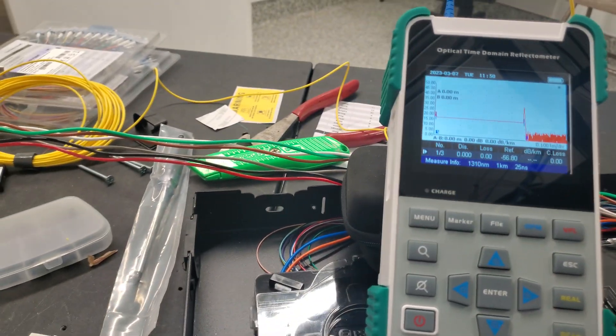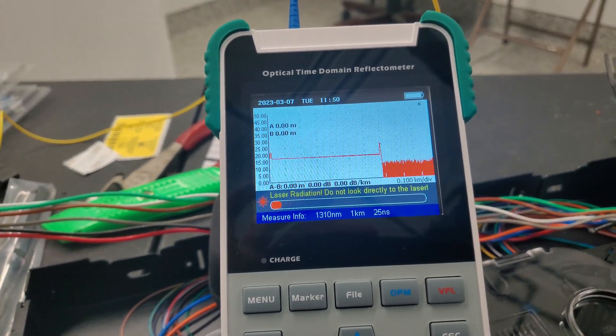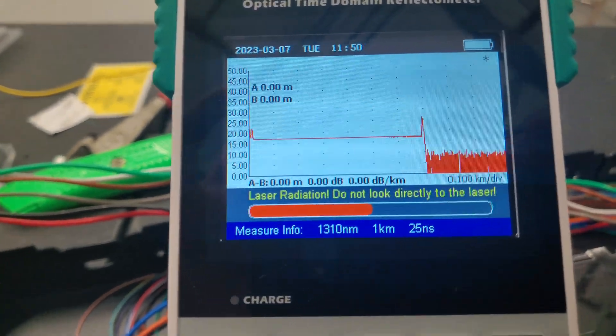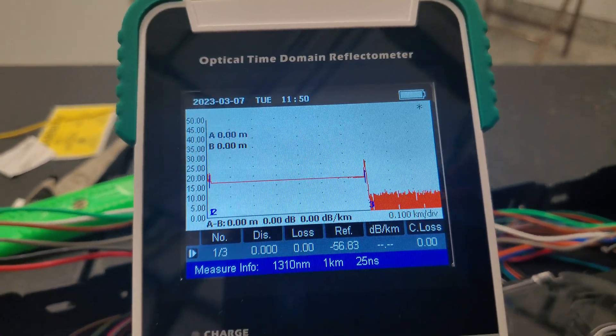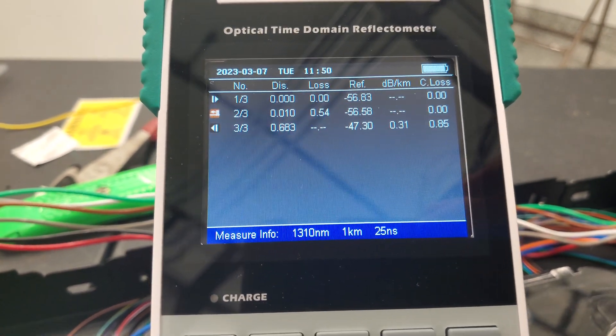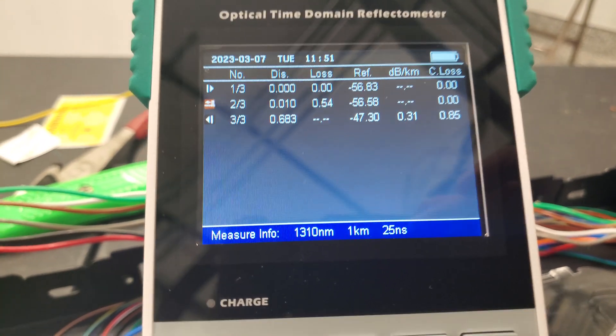I'm going to go ahead and escape and just pop this right over. For the most part they're all going to be about the same. Any major issue, now's the time to fix it because once this goes into the rack there's no bringing it back out. As you can see I'm sitting right about the same — that's probably my splice. It's hard to really tell being so close to it. I don't have any splices out in the field yet on this but one.